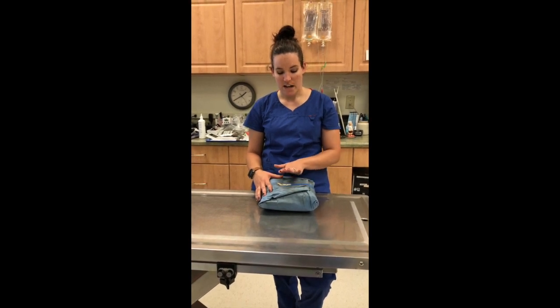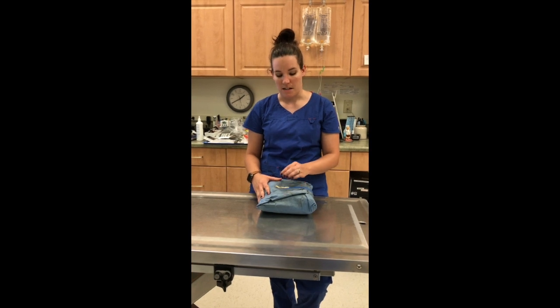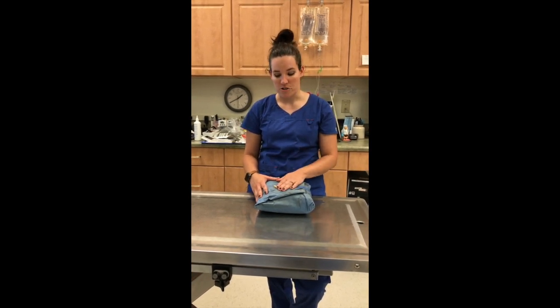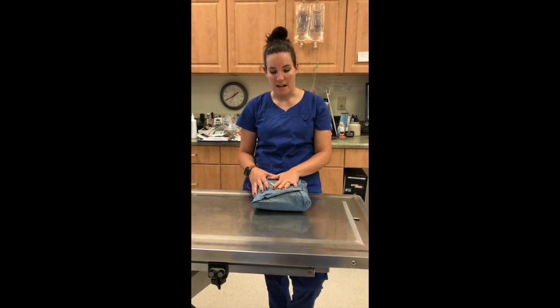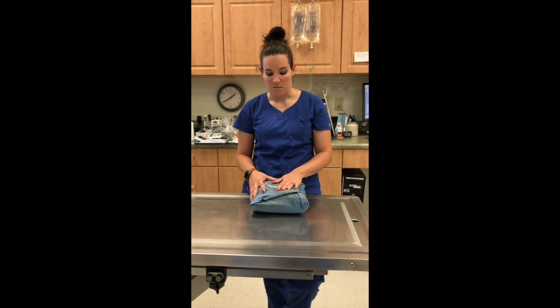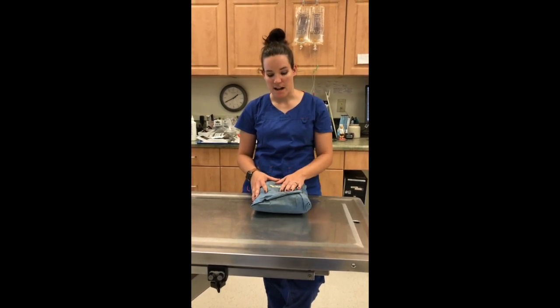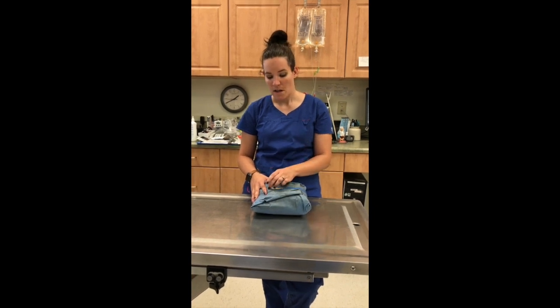These steam sterilizer indicators react to the heat as well as the time, and to a certain extent some of them, the pressure. And so for autoclaves, for a general pack like this, 250 to 270 degrees. They're going to hold it at 15 to 27 psi and anywhere from 3 to 15 minutes. For these big packs, typically it's a longer cycle.